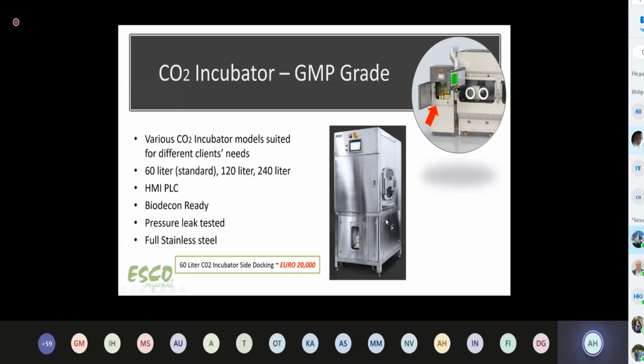If you look at this machine at the bottom, there is already a built-in biodecon system that can give you that 6 log reduction of the microorganisms. We will cover biodecon a little more later on. This incubator is also completely pressure tested. It is fully fitted with inflatable seals. It is not easy to leak, and it's very easy to connect to an isolator as shown in this diagram. Of course, we make it in full stainless steel by default.